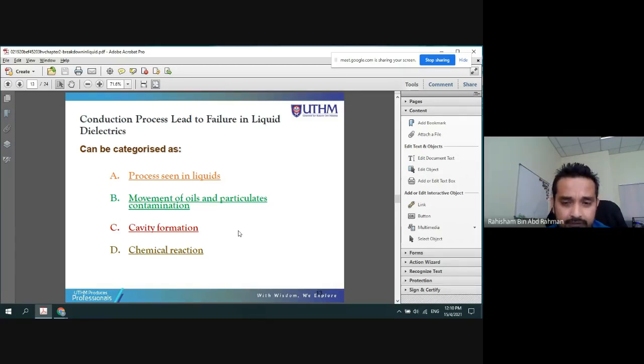An early treatment for the transformer oil is filtration. For example, after 2 or 3 years of service maintenance, we pump up the transformer oil and take it to the filter. We try to filter out as much of the metallic particles as we can, then pump it back to the transformer. That is what we call transformer oil filtration. The reason behind it is we want to get rid of the metallic particles in order to avoid conduction within the liquid dielectric.